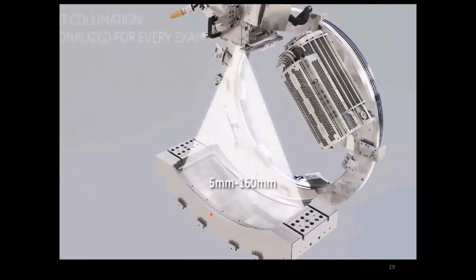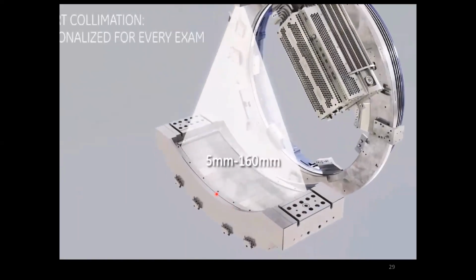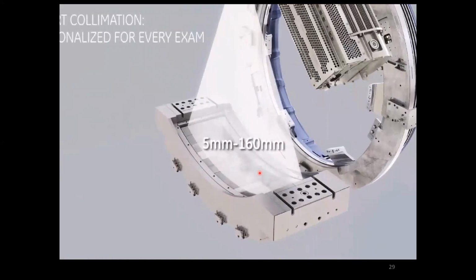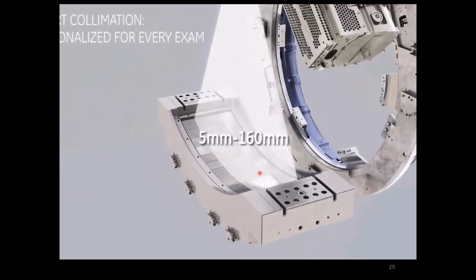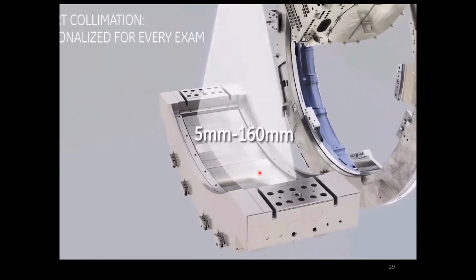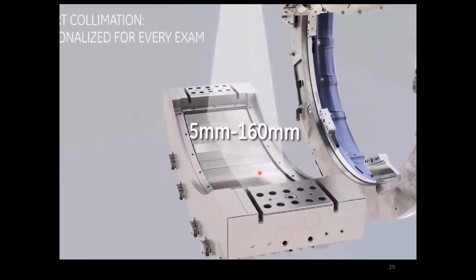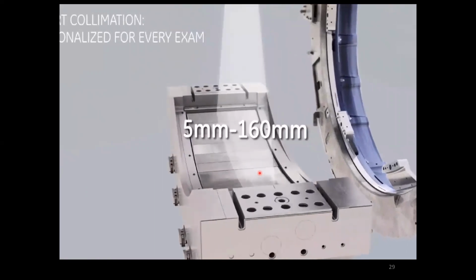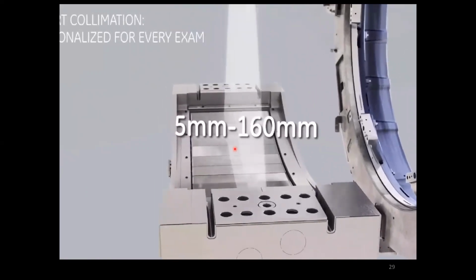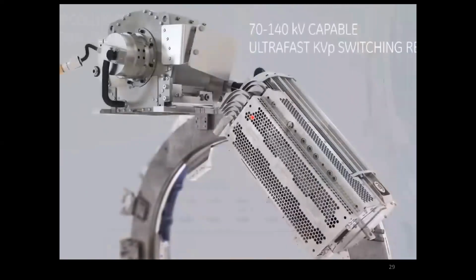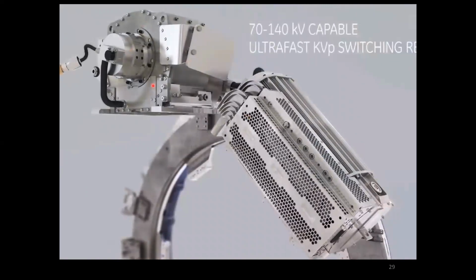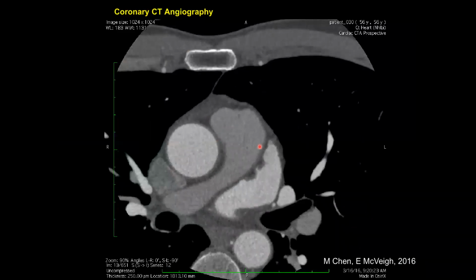And this is the detector array. It's about 1,000 by 256. So very low resolution for a camera, like on your phone. It's not 12 megapixels, right? It's 1,000 by 256. However, it's an X-ray camera, and it can collect X-rays really fast while they're getting shot out of this X-ray light bulb, right? And you can change the energy of the X-rays coming out of here. And so they get absorbed differently by the patient, and make pictures that look like this, right?